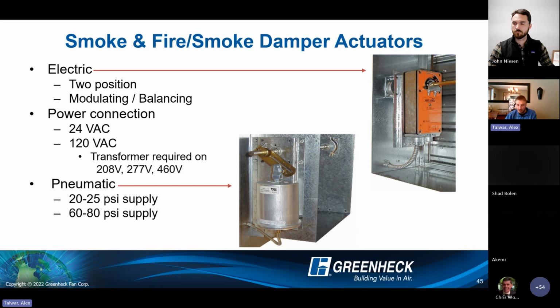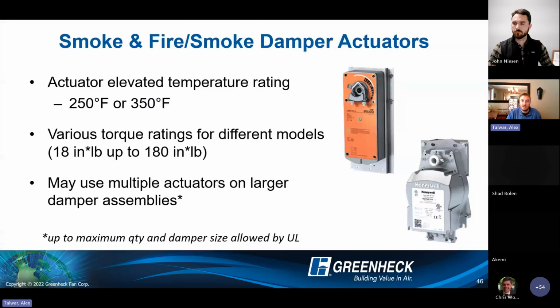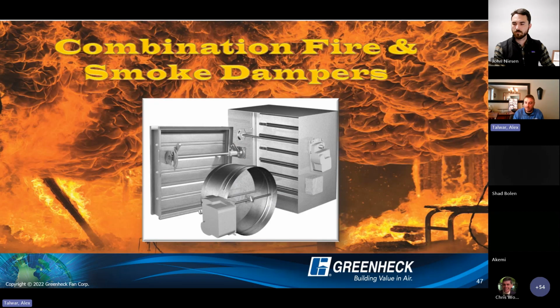So I'm not going to talk too much about pneumatics. I don't see those a ton anymore. And then quick recap on the actuator slide here. Larger dampers may need more than one actuator. So if we're starting to get into those large openings, large dampers, one actuator may not be enough. So we certainly may need more than one on those bigger models there. 250, 350, talked about that. And yeah, various torque ratings as well. So the actuator model is very closely tied into the damper product itself.